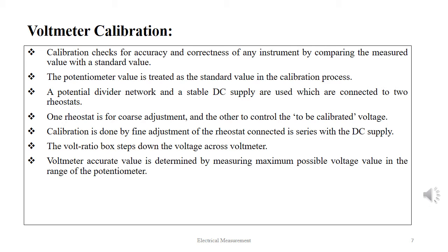One of the principal applications of a DC potentiometer is to calibrate devices like voltmeters, ammeters, and wattmeters. Calibration aims to enhance the accuracy and correctness of an instrument by comparing the measured value with the standard value. Here, the standard value is the potentiometric value.